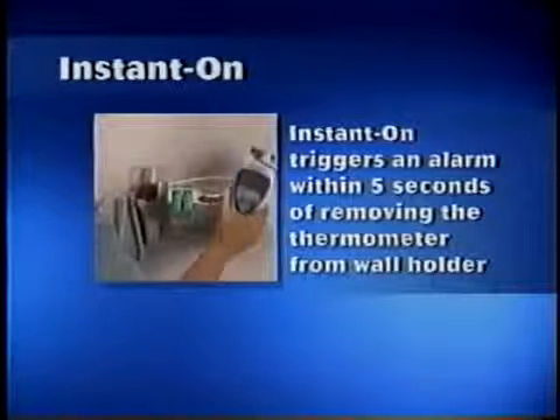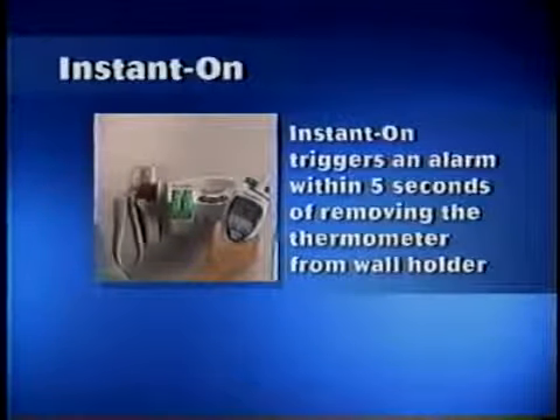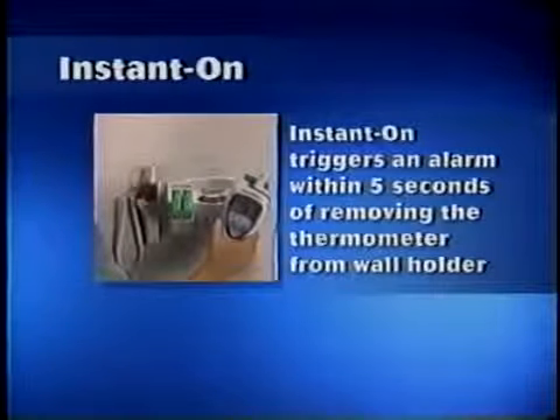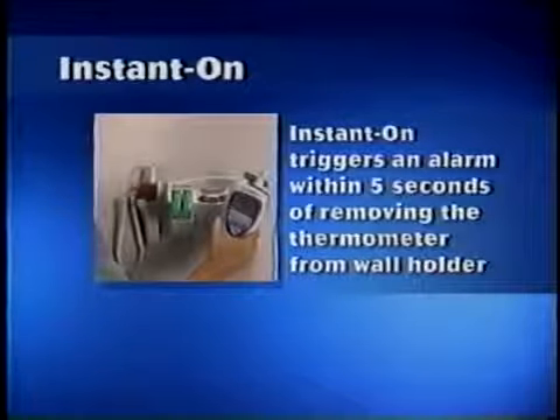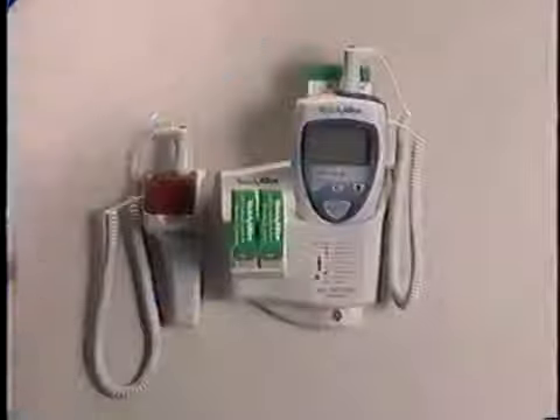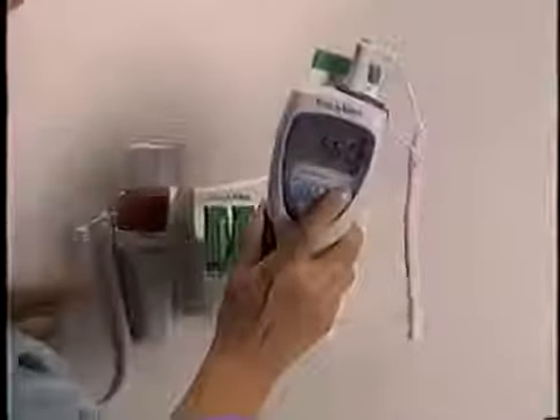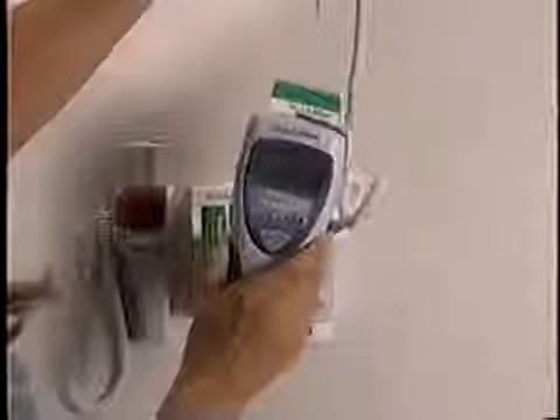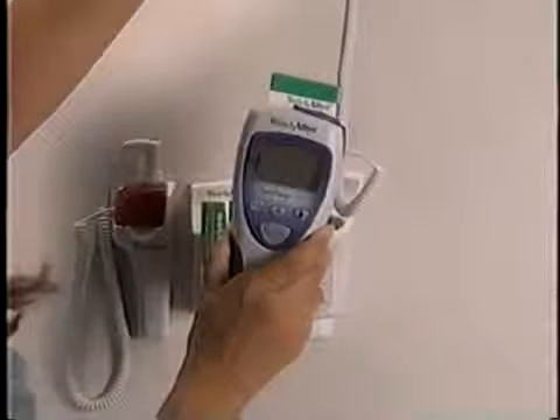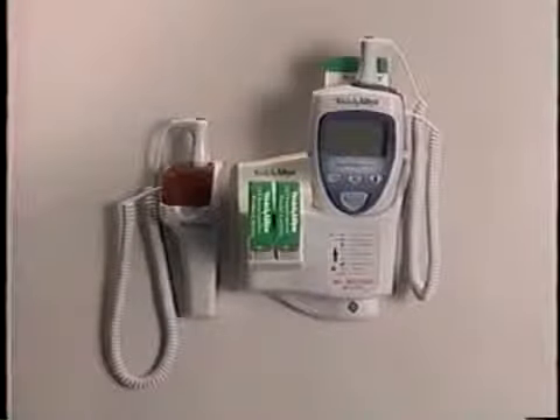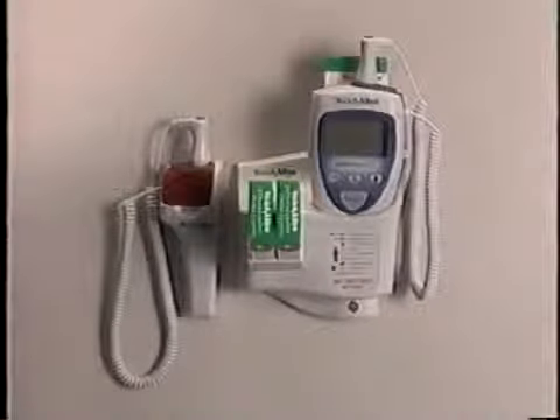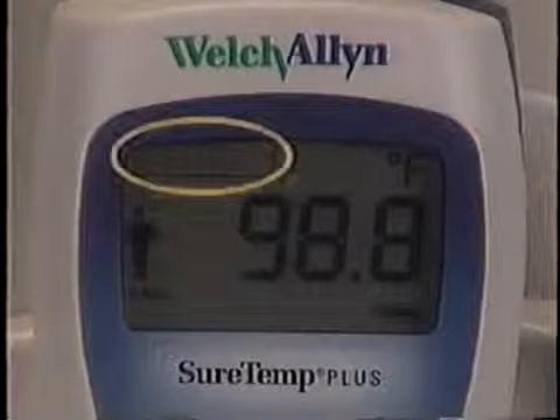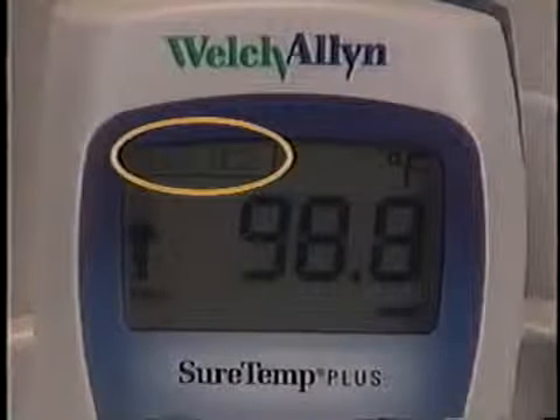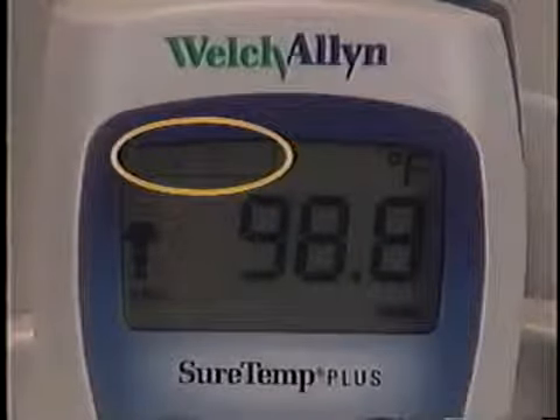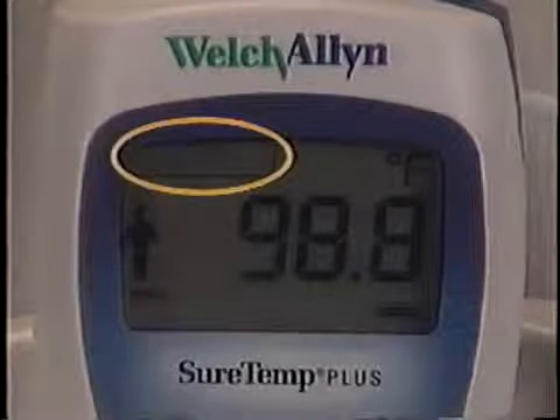The Instant On feature triggers an alarm within 5 seconds of removing the thermometer from the wall holder. When the alarm begins, the thermometer beeps continuously and displays SEC. To turn off the alarm, press the Mode Selection button while removing the probe from the well. You need to do this within 30 seconds of removing the instrument from the wall holder. Take as many temperatures as necessary and then return the thermometer to the wall holder to place it back in the alarm ready state. The Model 692 provides a 7-character ID field for customized identification of the instrument. This feature helps you track thermometers and assign them to specific locations in your facility.